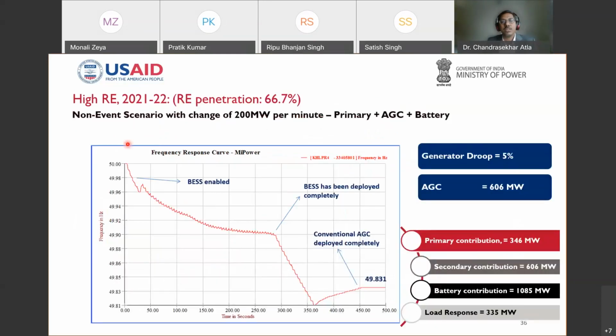And taking it forward, we initially discussed what happens to my primary and secondary reserves if more and more renewables are added into the system and those renewables change dynamically. So for the 21-22 scenario, if the renewables change, a combination of wind or solar, whatever it may be, at 200 megawatt per minute, is the designed battery of 1085 sufficient to maintain the frequency and keep the system within the limits or not?